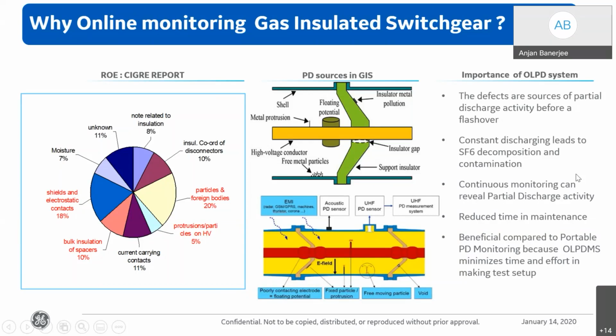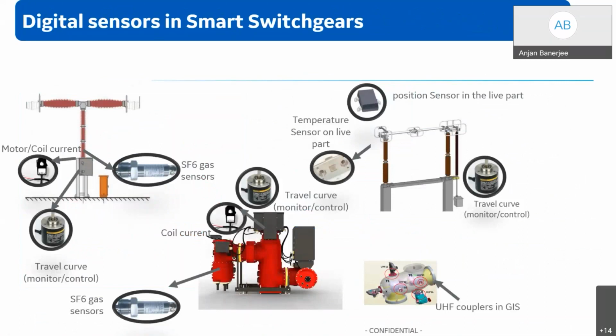So partial discharge activity must be monitored within GIS on a real-time basis. An online monitoring solution can help us to monitor partial discharge activity within a GIS compartment. Now, when we talk about online monitoring or digital solutions, we also have to make the switchgear smart enough by embedding intelligent digital sensors within it.